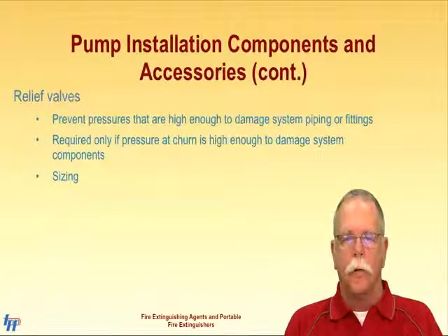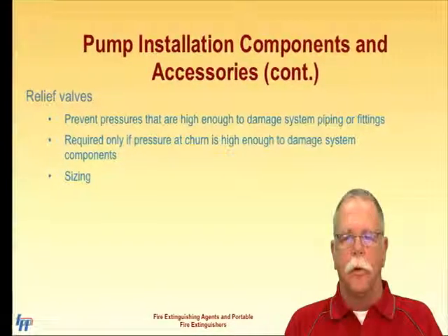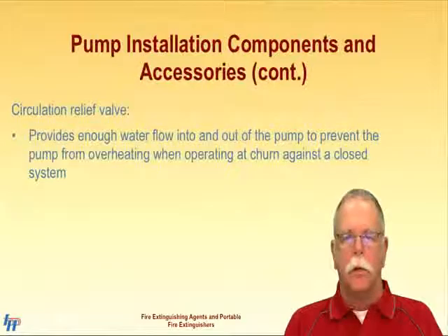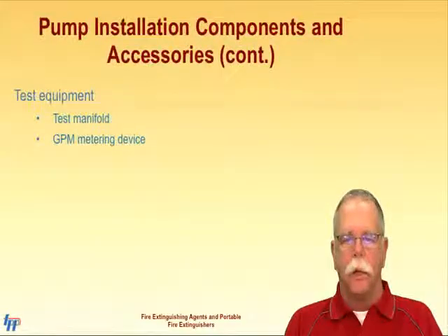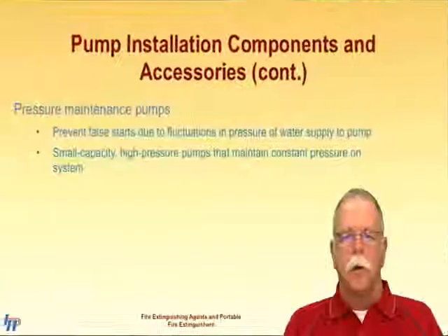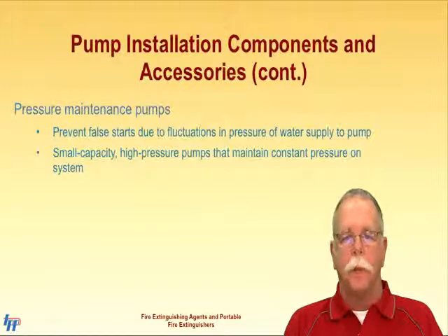Relief valves used to be installed to prevent overpressurizing the system in the event the driver ran too fast. Relief valves on fire pumps are now required if the pump pressure is enough to damage the system components while at churn. Churn is when the pump is running, but all discharges are closed. Size of relief valves and piping is determined by the pump capacity rating. The relief valve should be set to open at a pressure slightly higher than operating pressure.